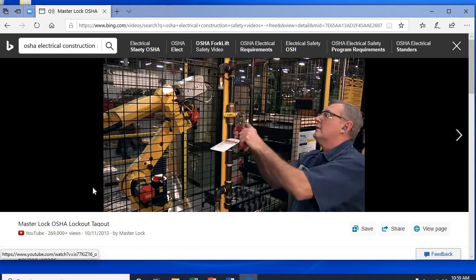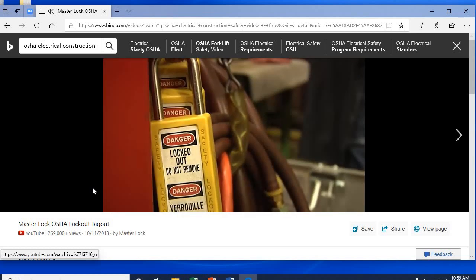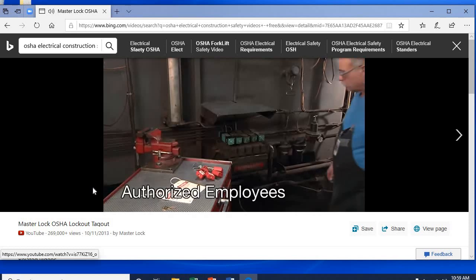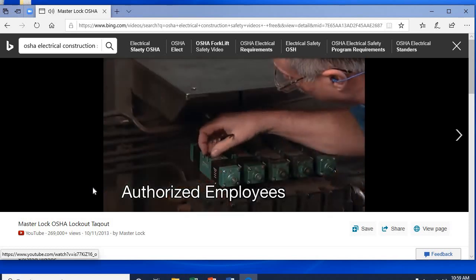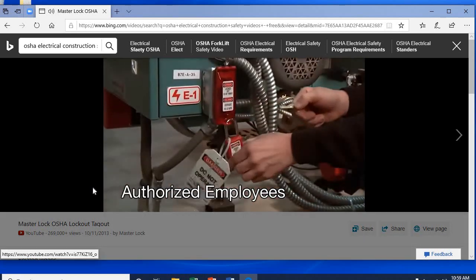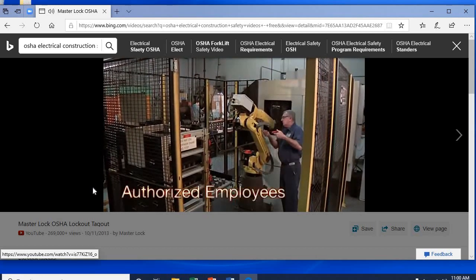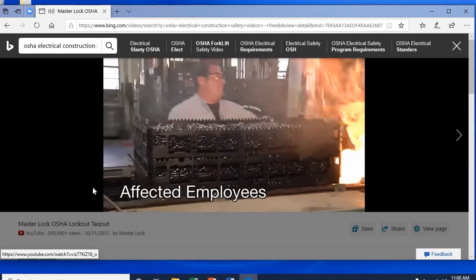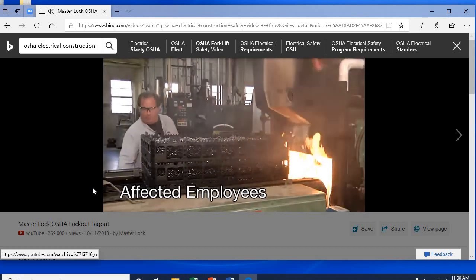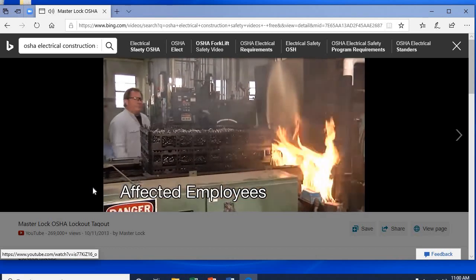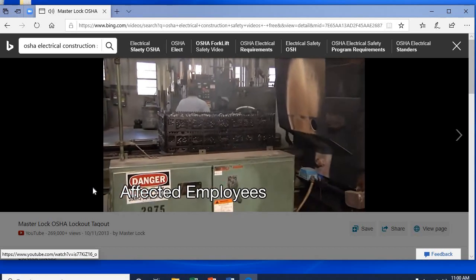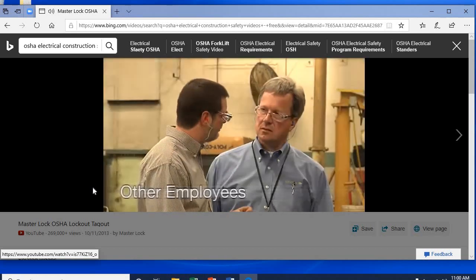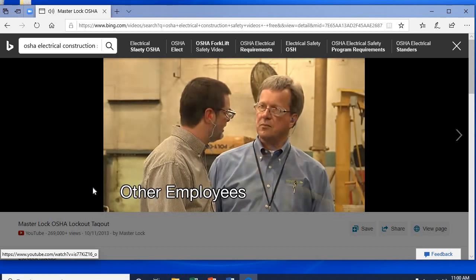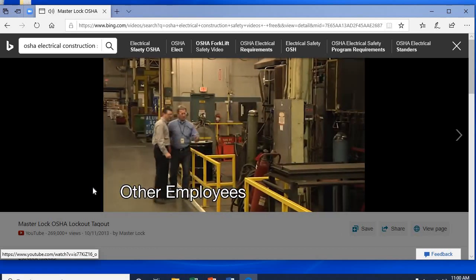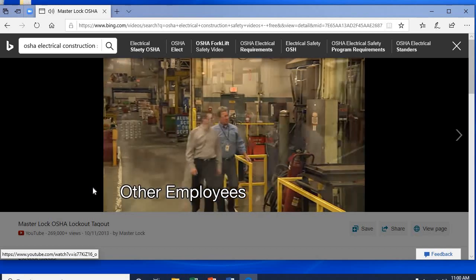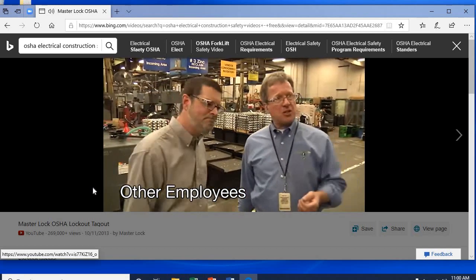Lockout impacts a variety of workers at a facility. The three categories are authorized employees. These are the workers specifically trained to lock out or tag out equipment in order to service or maintain the unit. Affected employees are the ones who work with or near the equipment being serviced. They are trained to recognize the lockout but not perform it. And other employees are those who work in or near an area where lockout-tagout may be used. They also need to be instructed to recognize lockout but not perform the lockout procedure.